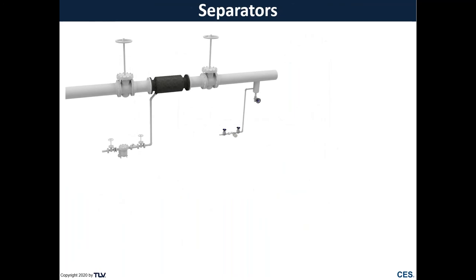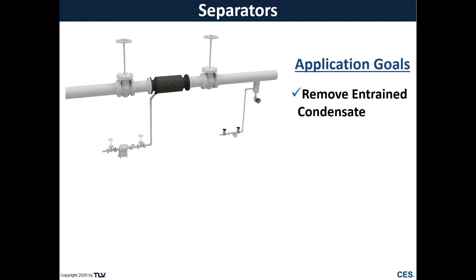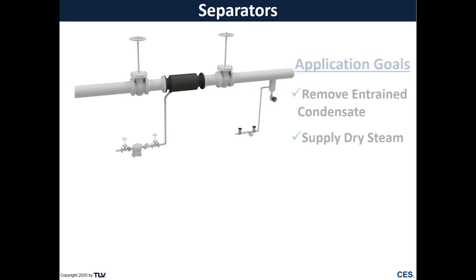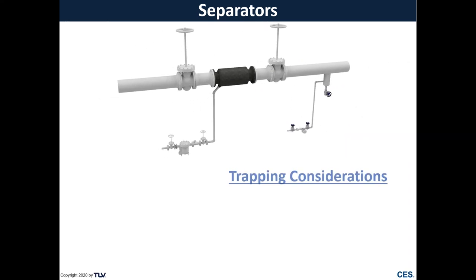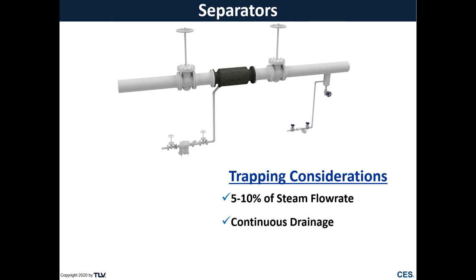Another location is a steam separator in our header. Now the goal of a steam separator is to remove entrained condensate from your steam main and to supply dry steam throughout your plant. So our goals here are that we need to remove a potentially high amount of condensate. And typically we size that for at least 5 to 10% of the overall steam flow rate through that pipe. And we're going to want something with continual drainage.